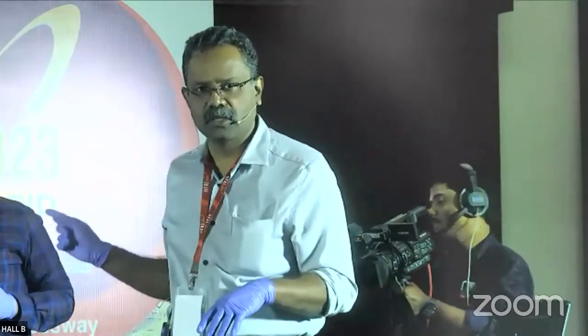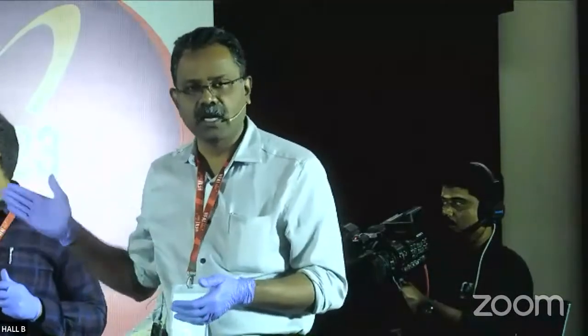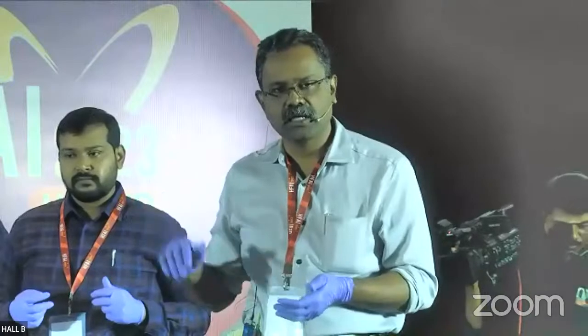One is the return cannula, one is going to the arterial system, and one is going to the venous system. So if you don't put the tube occluder, most of the blood will go to the venous system because it is a low pressure chamber. So if the venous system is going to receive around 3 liters of blood, and the arterial system is going to receive only 1 liter of blood, then your MAP and other things will fall. The very purpose of VA ECMO will not be served. So you have to put the tube occluder to maintain a saturation of around 85%. The remaining blood can go through the arterial system, and you can maintain the MAP.